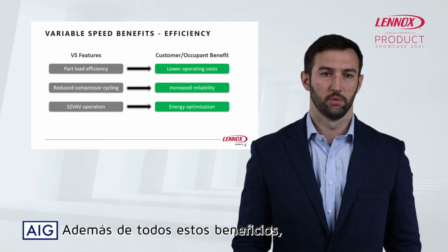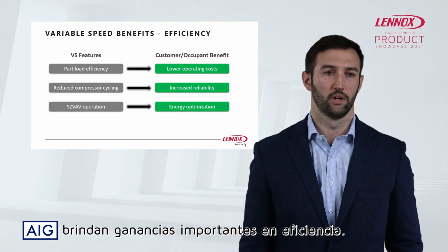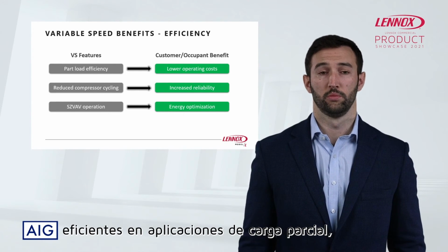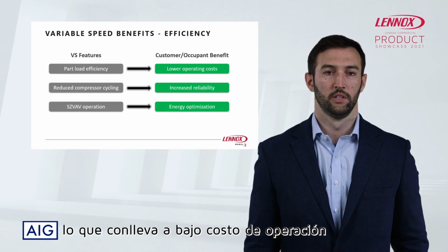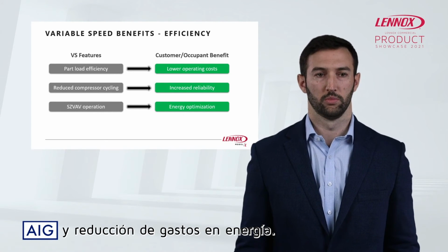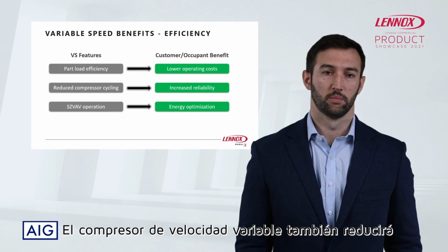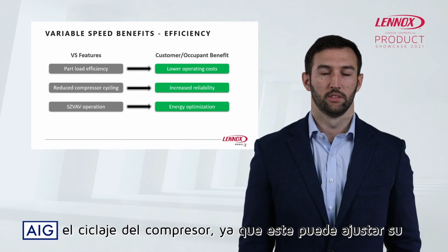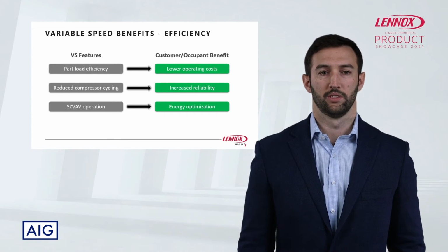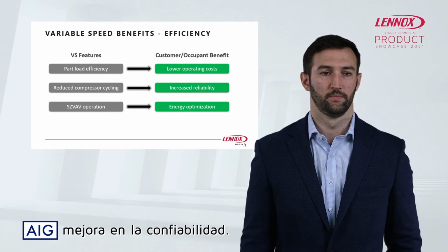Along with all the customer benefits, variable speed compressors also provide great efficiency benefits as well. The inverter-driven variable speed compressors are extremely efficient in part load operation and applications, which reduces operating costs and lowers energy bills for our customers. The variable speed compressor will also reduce compressor cycling, as it can vary its speed to match the load in the space. This is going to result in less wasted energy and increased reliability for that customer.